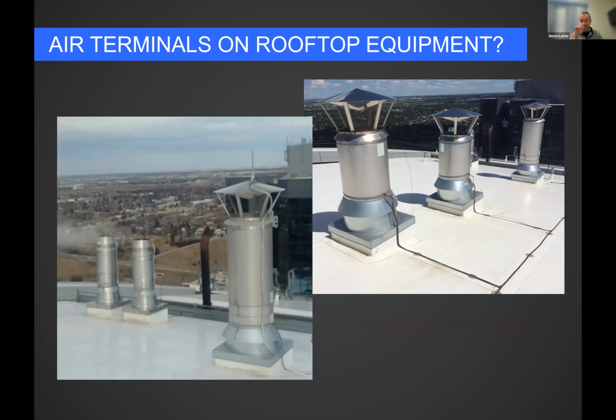Is there protection on the rooftop equipment? This is something I used to see a lot, but I'm seeing less of it as code develops and installers change their practices. In the 1987 code, you were permitted to simply bond rooftop metal equipment with a single conductor and call it a day—you can see that in the right-hand picture, a high rise here in Calgary with just a single metal strap bonded to those vents. Presumably, if lightning struck those vents it would travel through that strap to the lightning protection system. The problem, even as accepted code practice back then, is that you're not guaranteeing the lightning current will actually follow that 1-inch wide copper strap.